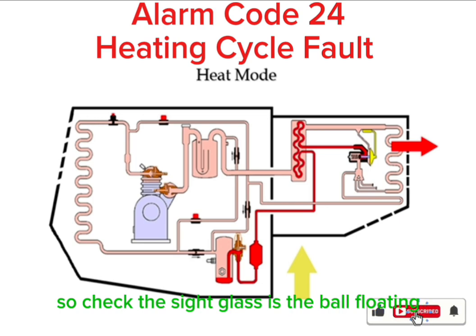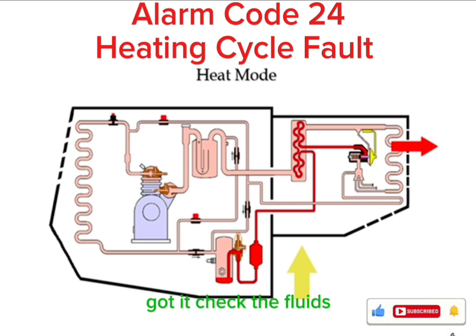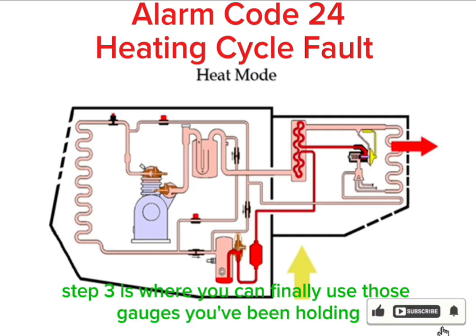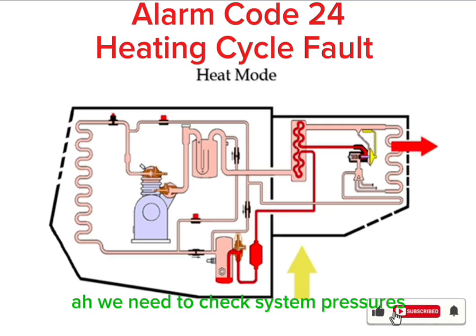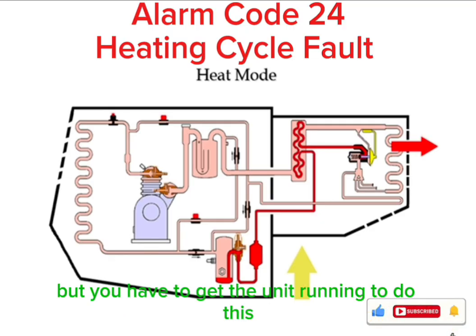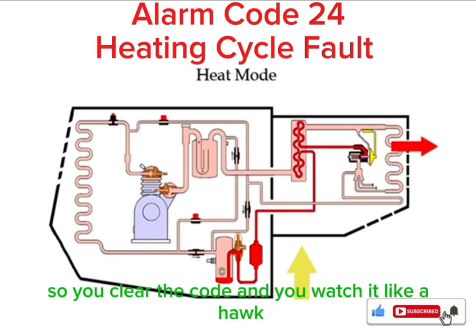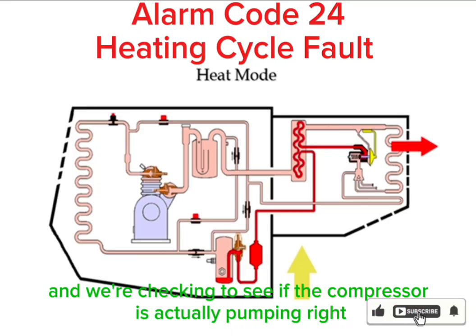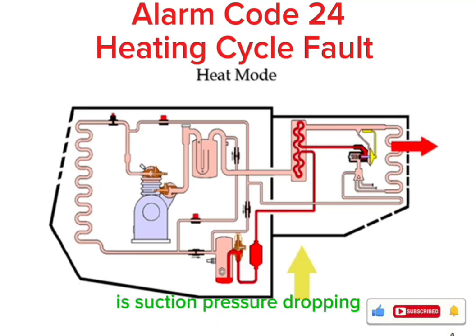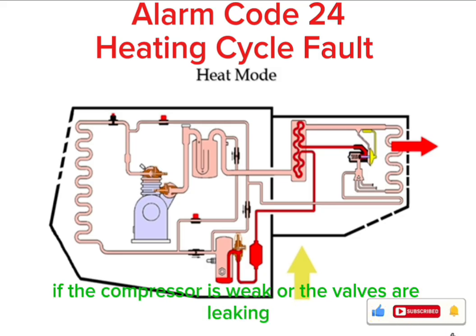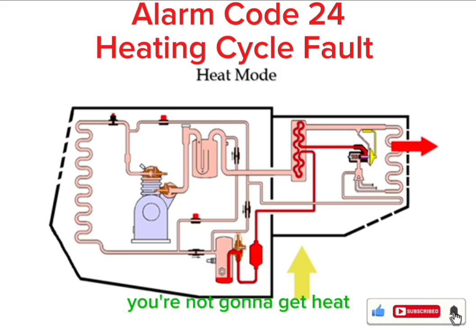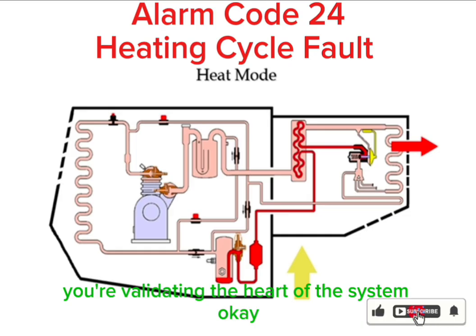So check the sight glass. Is the ball floating? Got it. Check the fluids. What's step 3? Step 3 is where you can finally use those gauges you've been holding. We need to check system pressures, but you have to get the unit running to do this, so you clear the code and you watch it like a hawk. And we're checking to see if the compressor is actually pumping. Right. Is suction pressure dropping? Is discharge rising? If the compressor is weak or the valves are leaking, you're not going to get heat. You're validating the heart of the system.